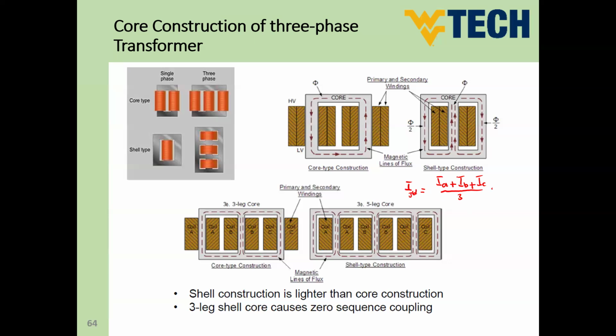If you compare that to the neutral current of the Y connection, you know that I neutral also equals IA + IB + IC, which means that if you have neutral current flowing in the neutral wire, this would be a third harmonic. Third harmonic is one of the zero sequence components. So the shell will provide zero sequence, and this is one advantage of the shell compared to the core. You have zero sequence coupling, but core cannot have zero sequence, and this is the difference between both. So shell construction is lighter and preferred because of the zero sequence coupling.